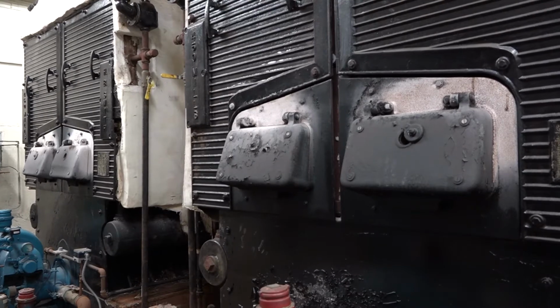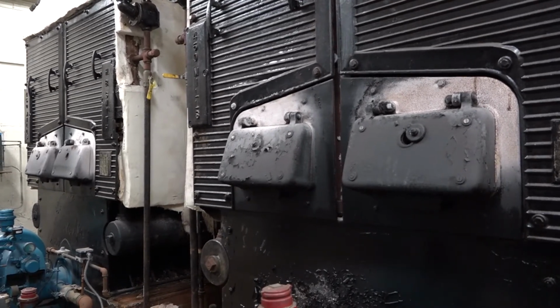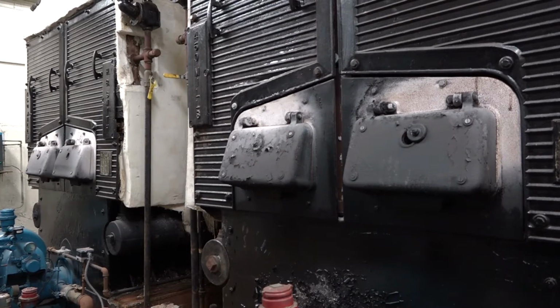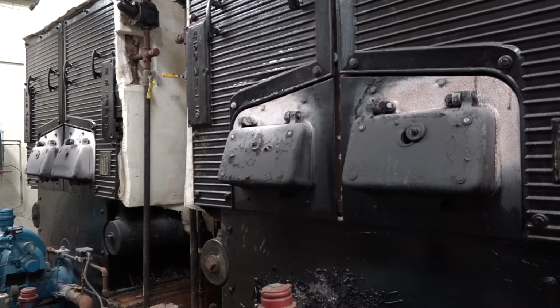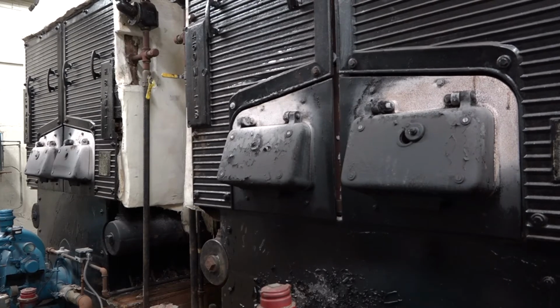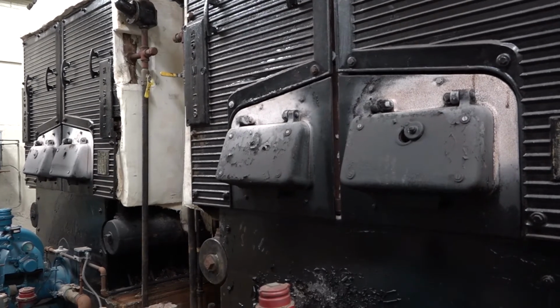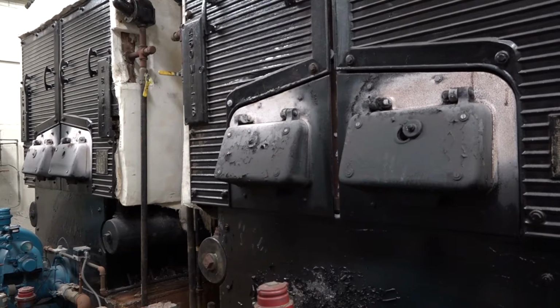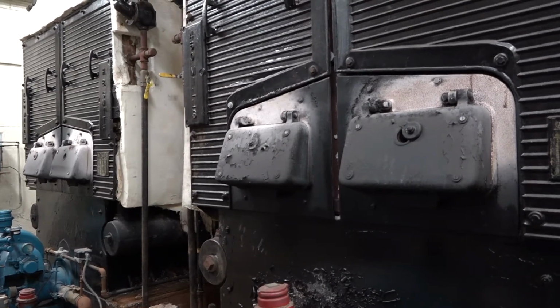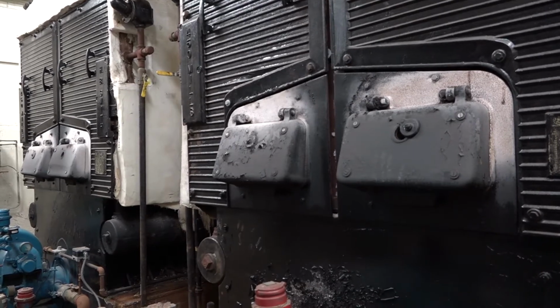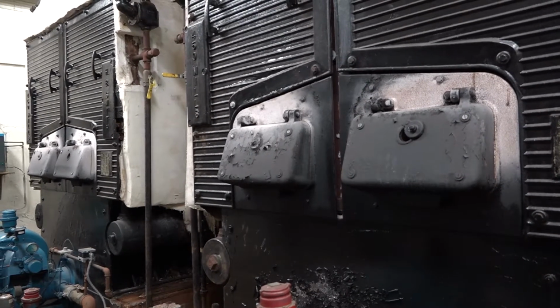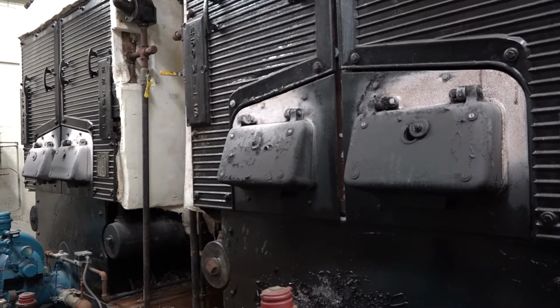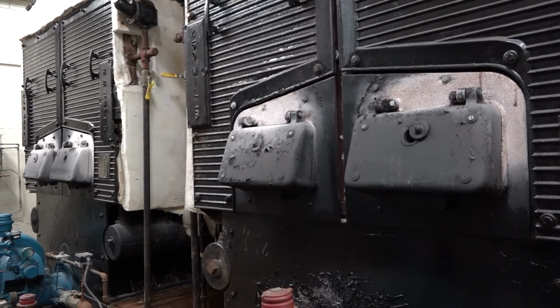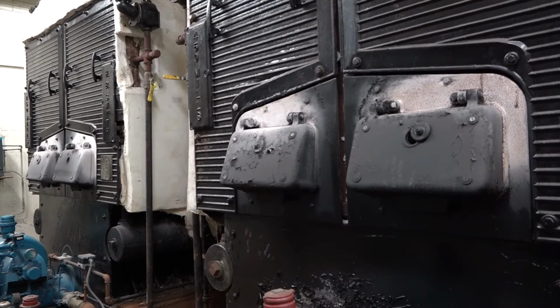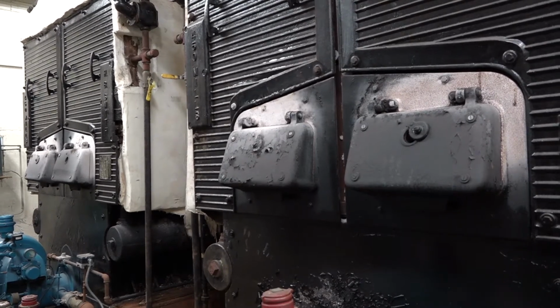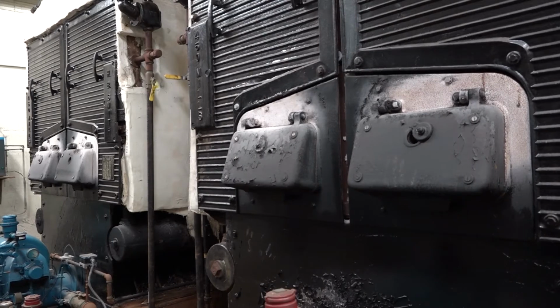And the heating system in here is still pneumatic, pneumatic thermostats and heating valves. The new additions are hot water, forced hot water, so we've got a heat exchanger up top that will video so people can see where the steam exchanges over to hot water. We just replaced one of those heat exchangers a few years ago due to its age, and that tank rotted out as well. So two circ pumps up top feed the hot water system. And also the main electric room is right up top here. We'll take a walk up and look at those as well.